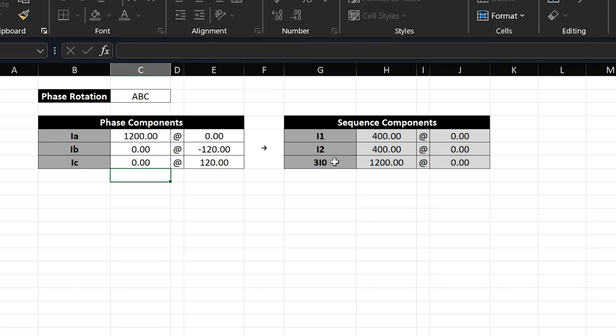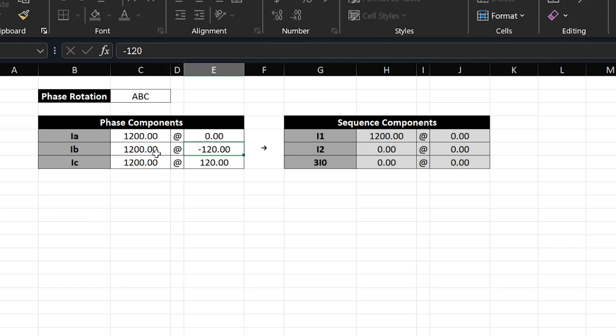Now let's say we had another example where we had balanced currents — so the B and C phase currents are also 1200 amps, and these are balanced as you can see from the angles. For this case we would expect purely positive sequence current since there is no imbalance in the system. The three phase currents are balanced, and over here on the right for the symmetrical components we can see that we only have positive sequence, and its magnitude and angle is equal to the A phase current.